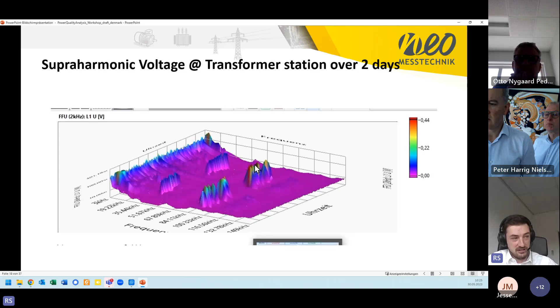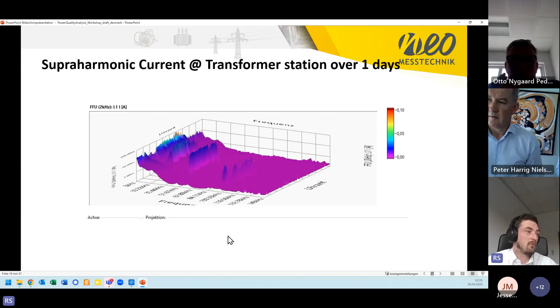For the current, we did more or less the same measurement. Here, over one day, we also see at 80 kilohertz a higher frequency current at the transformer station. So the effect is already there, I would say, and therefore we need to be aware of it. We need measurement equipment that can do this analysis, that is able to measure this in the first place, and give us the chance to act. Otherwise, you're looking in the dark and you'll find nothing.